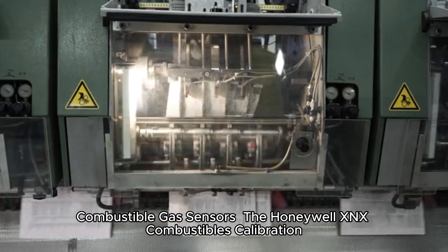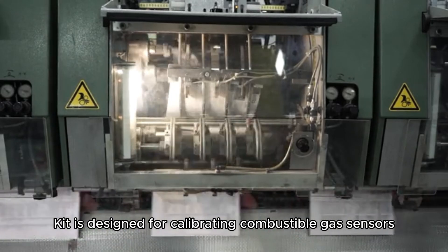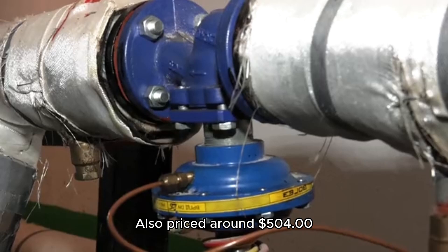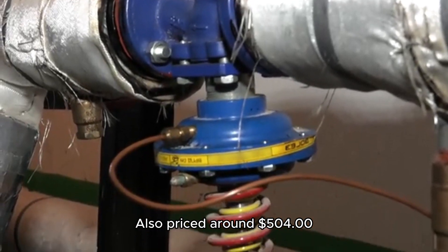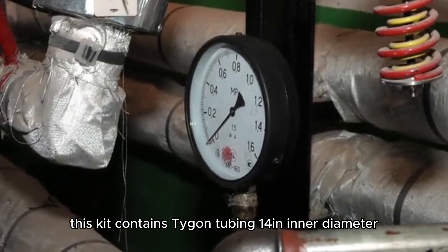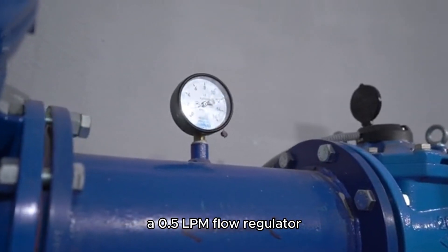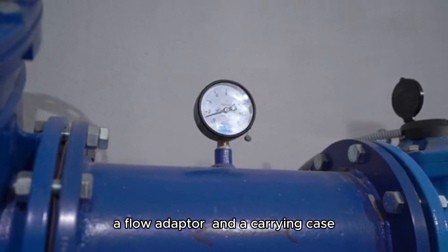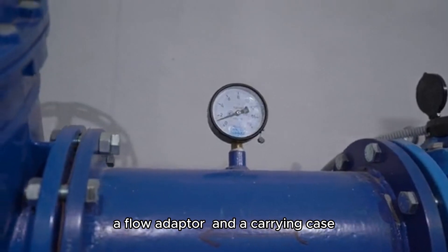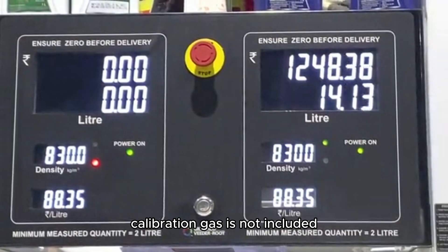The Honeywell XNX Combustibles Calibration Kit is designed for calibrating combustible gas sensors. Also priced around $500, this kit contains Tygon tubing (1/4 in inner diameter, 7/16 in outer diameter), a 0.5 lpm flow regulator, a flow adapter, and a carrying case. Similar to the Toxic Calibration Kit, calibration gas is not included.